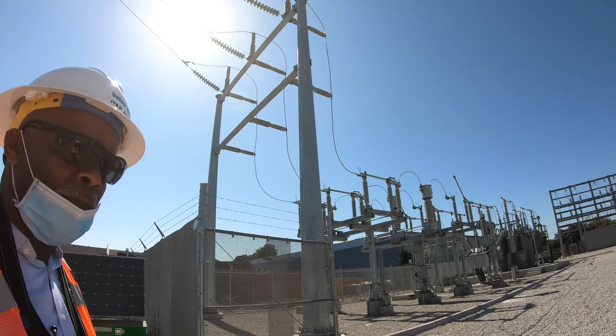As we walk through the substation, what appears to be a complex network of equipment is relatively simple and straightforward. This particular device here is the PG&E disconnect switch, which allows them to manually disconnect the 115 kV from the substation. The next device is a PG&E metering junction box, and that's analogous to the power meter in your home. And that's the device that PG&E will utilize to measure the amount of electrical power utilized by the future system.